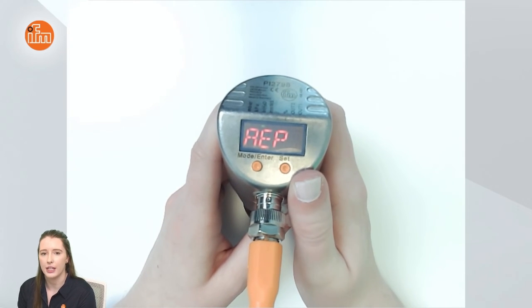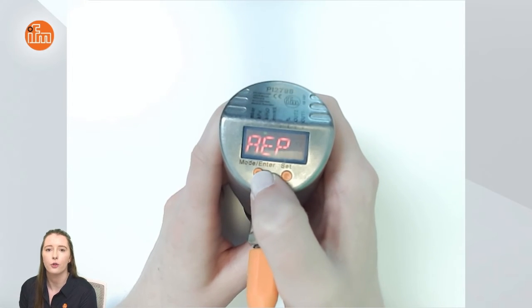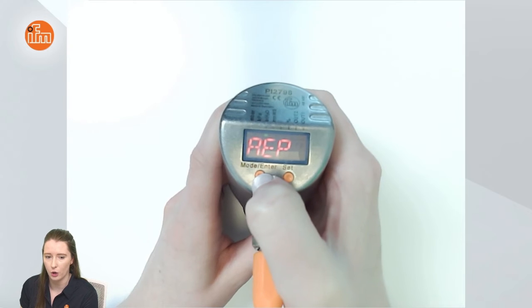So currently my 4 to 20 milliamp output would be scaled for 0 to 26 inches of water column.